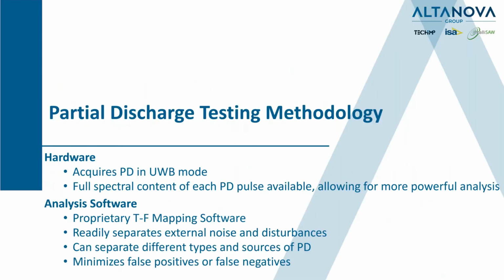All right. So let's talk about partial discharge testing methodology. First, we acquire the PD in ultra-wide bandwidth mode. What does that mean? Well, basically that means we're in the megahertz. So it's anywhere from 30 to 300 megahertz. And we also use the full spectral content of each PD pulse, and you'll understand what I mean by that here in a minute, okay?